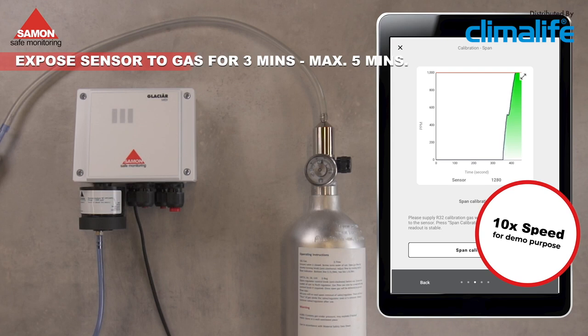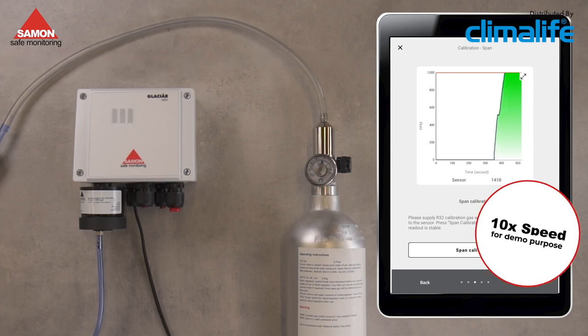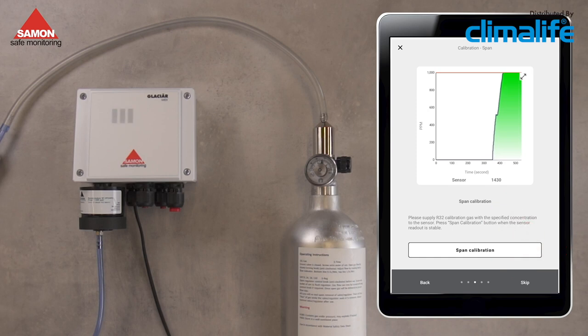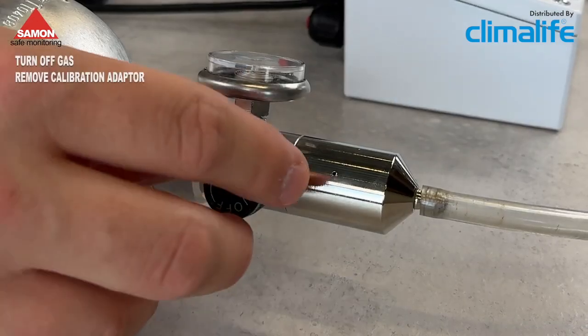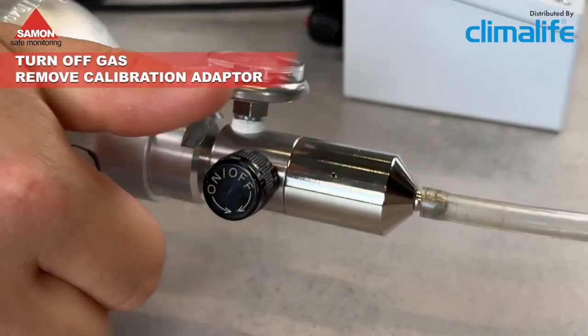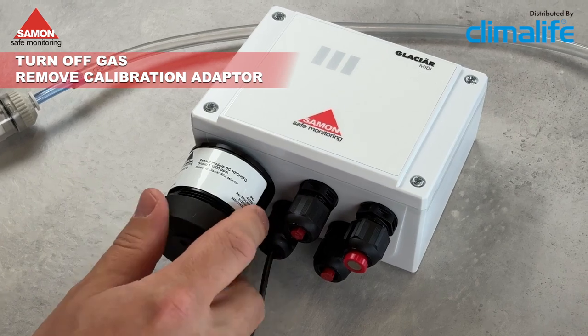The sensor should be exposed to the known gas concentration for a limited time. The recommended time is 3 minutes, maximum 5 minutes. Looking at the sensor value in the app, when the sensor value has stabilized, click Span Calibration in the app to save the calibration. You can now turn off the gas and remove the calibration adapter from the sensor module.